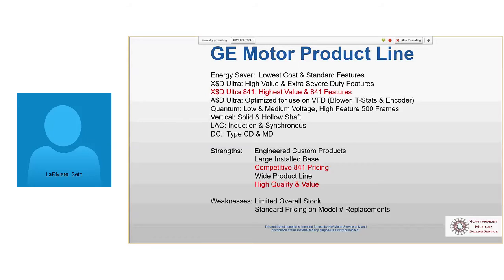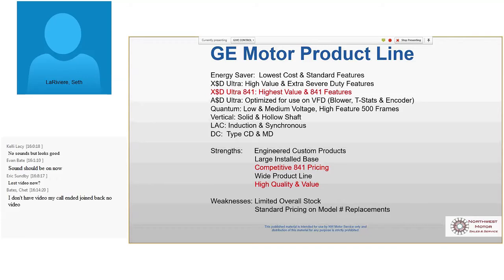So if that $2,000 motor, and you're talking the delta between the best motor you can buy and the cheapest is maybe a couple hundred dollars or 10%, so you're talking 200 versus 2,200. But you're going to spend 75 grand running that motor in the first year. My motor is only going to cost 68 grand to run in that first year. There's a real easy payback.